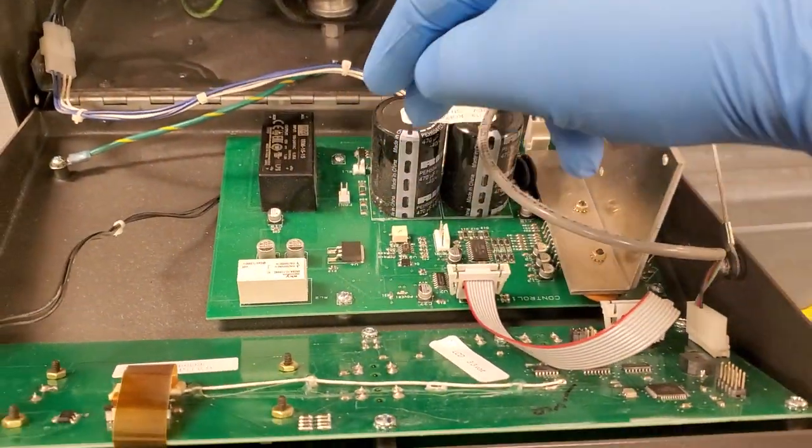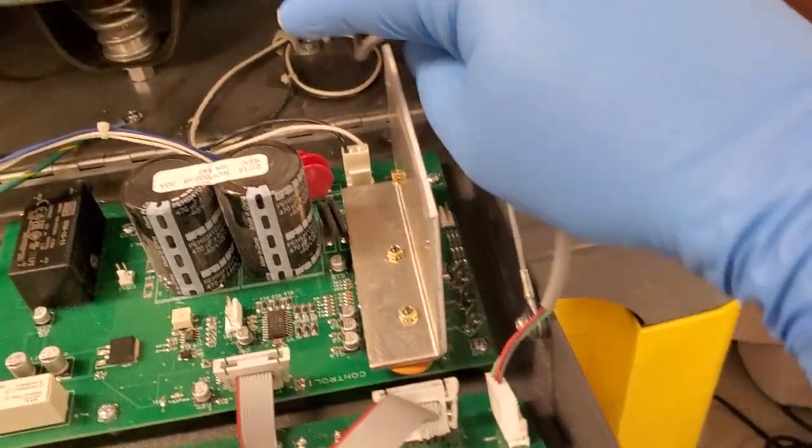First off, I've got the motor out of the centrifuge. You can see this here is just the front faceplate - it's an interface board. At the back here is both a power supply because you have mains that comes into it, the black and white, and right here you see the three terminals for your motor output.